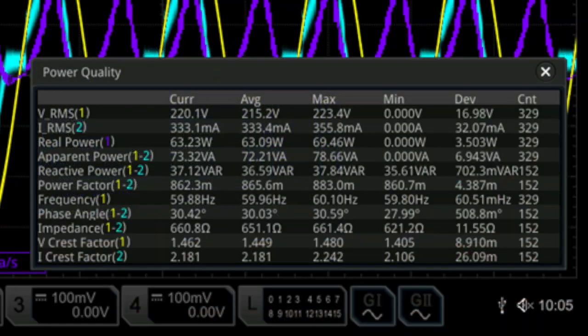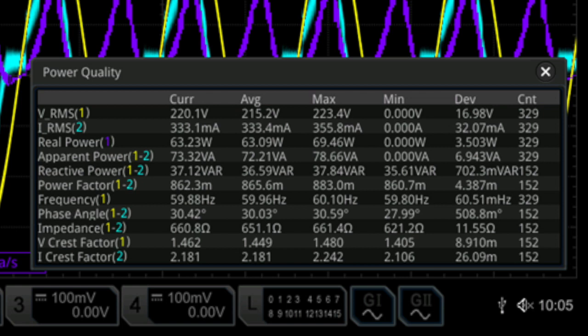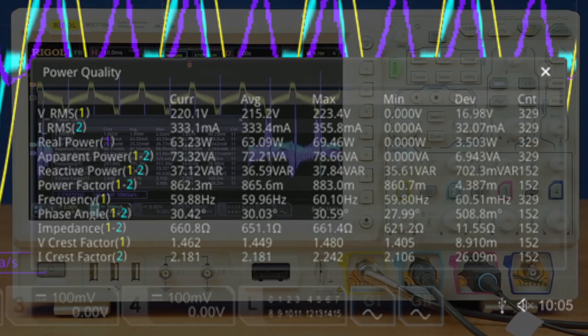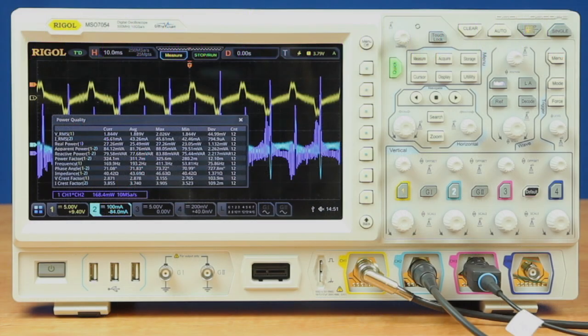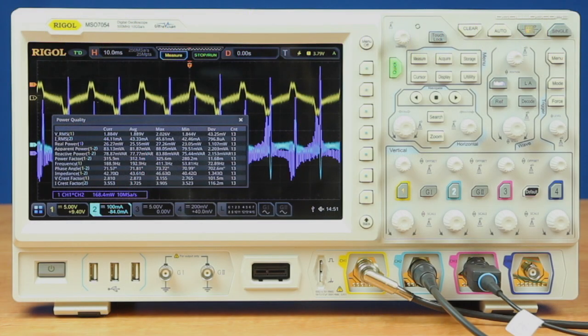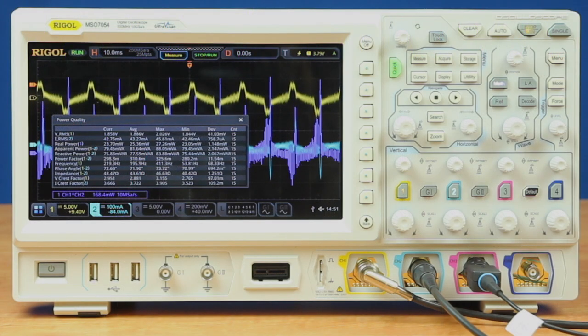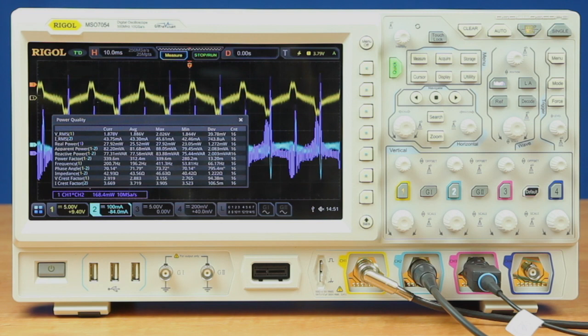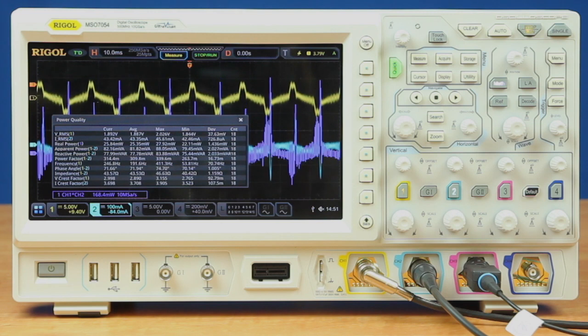Power quality measurements make specific measurements of these 12 important characteristics of your power quality. We can do hundreds or even thousands of counts and average them and look at the deviation on all. This is a great way to test the operability of your switching power supply as you're getting through an embedded device test.